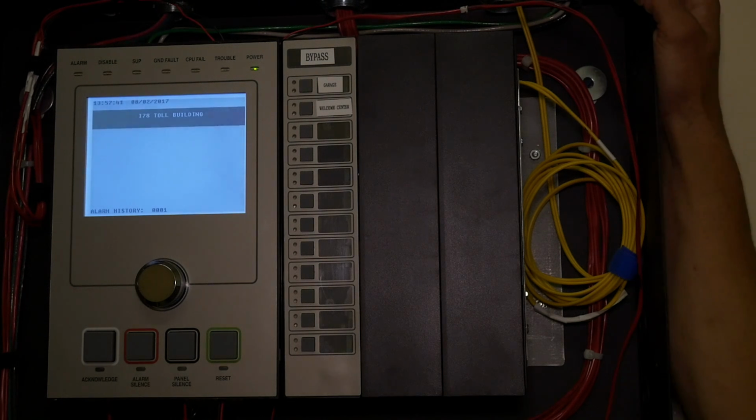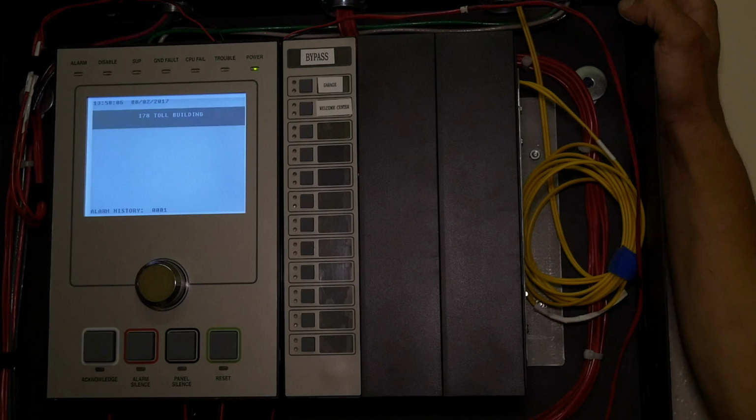Okay, now, in a situation where there's a fire near our air handler and the detector goes off, does that automatically shut down the air handler so it doesn't throw smoke throughout the building? No, the way that this building is programmed right now, there are no relays to shut units down. Those would need to be added to the system in order to do that.